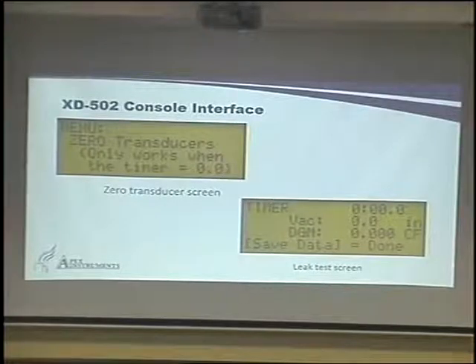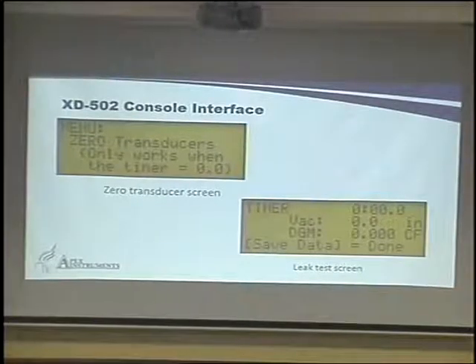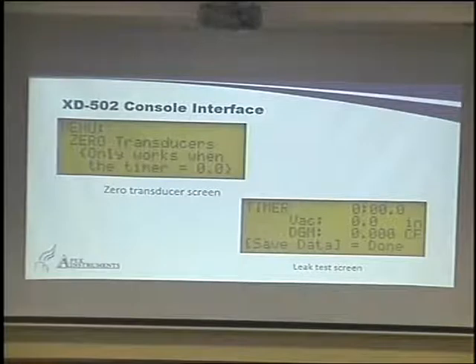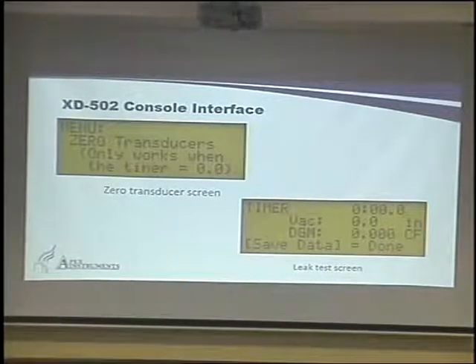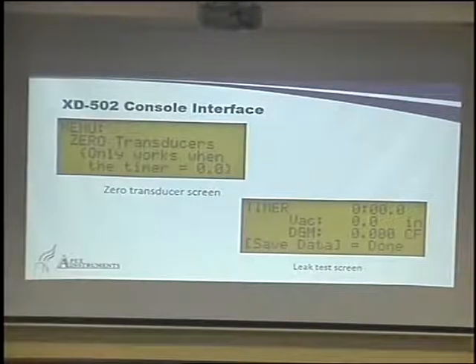So we've got a unique and standalone leak test screen. So your pre-leak test and your post-leak test are recorded as separate values within the software. So you as a tester can prove either to the management of your company or to the customer that yes, we performed a leak test before we started sampling, and we performed a leak test after we finished sampling. We passed the leak test, and here are the values that we got.